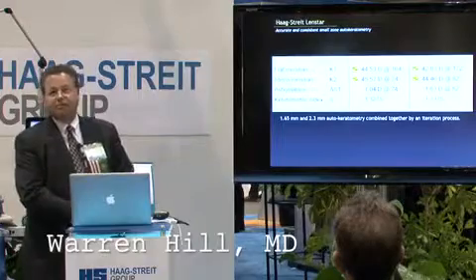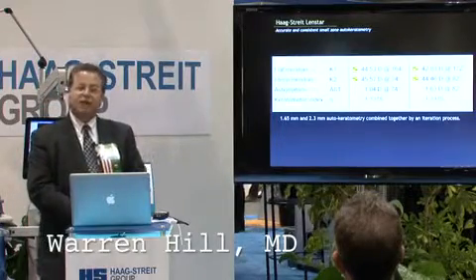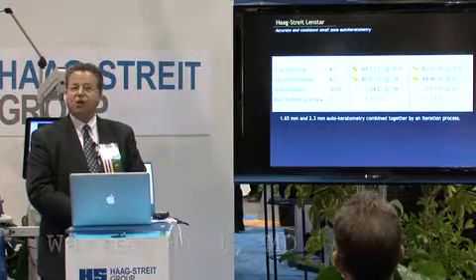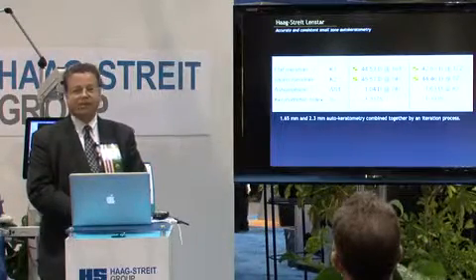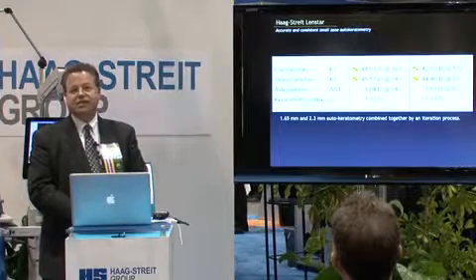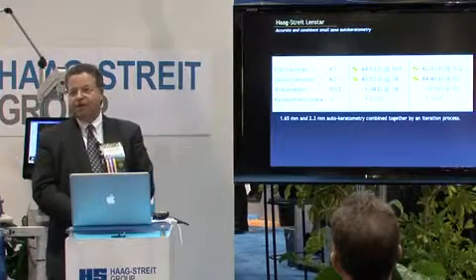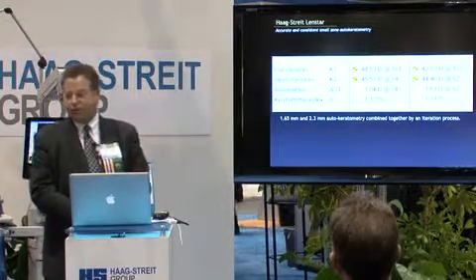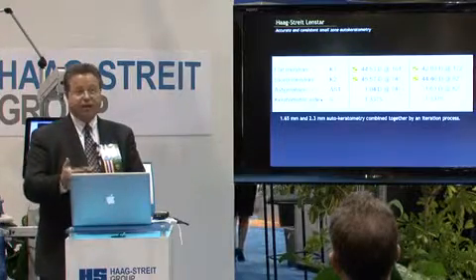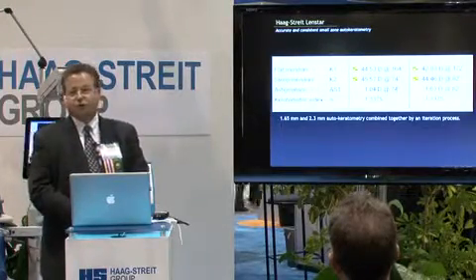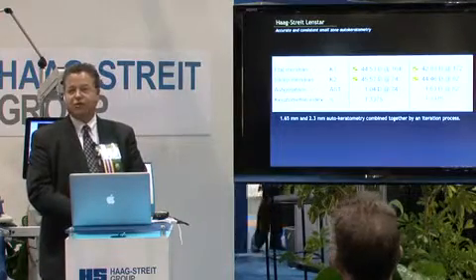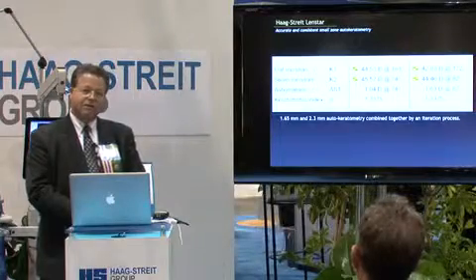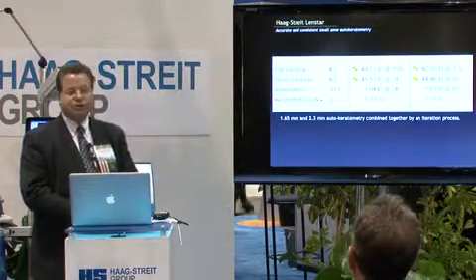The part that I really like a lot about this instrument is the keratometry. The Ks turned out to be a little bit of a surprise — they're probably the most consistent Ks we've ever seen. With the new software, David Cook has shown us that if the standard deviation is 0.34 diopters or better, you can use this for the toric IOL as your only measuring device. This is the first time we've been able to say this about an automated device for the toric IOL.